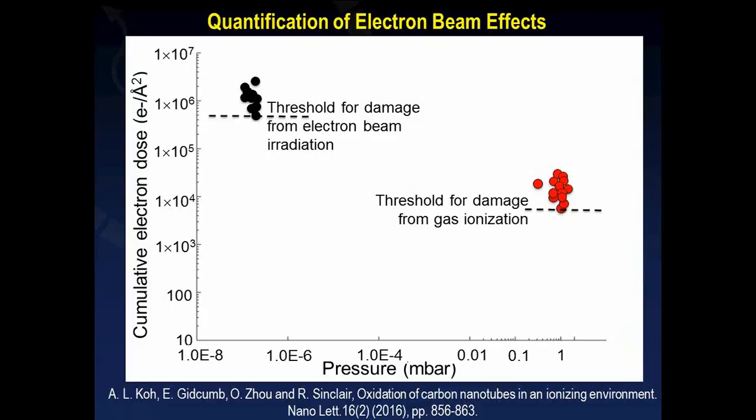For gas experiments, something as fundamental as what type of TEM grids to use matters a great deal. For a hydrogen experiment, I would never encourage anyone to use TEM grids with a carbon support film, because the carbon might react with hydrogen and form hydrocarbons during the experiment. It's not so much a mistake per se, but rather the rigor of experimental planning becomes ever more important for in situ experiments to do the proper and actual experiments.